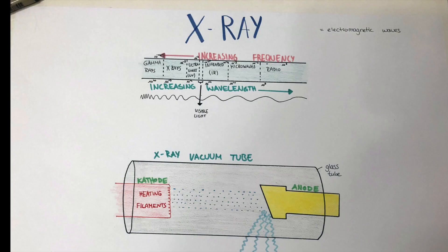X-rays are produced when high-energy accelerated electrons with a high enough velocity collide on a type of solid matter. This whole process is made possible within a tube — a so-called x-ray vacuum tube — which is usually made out of some sort of glass and creates a vacuum to prevent any interference, so that the electrons can freely flow from the cathode quickly into their target, which is the anode.